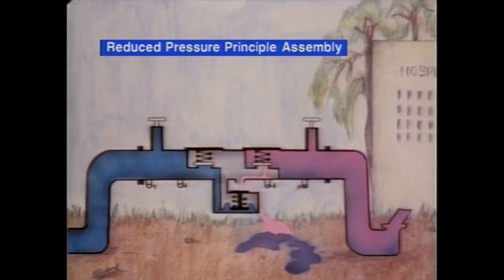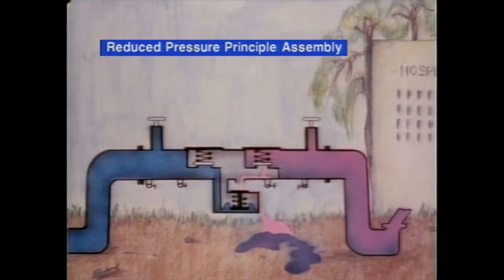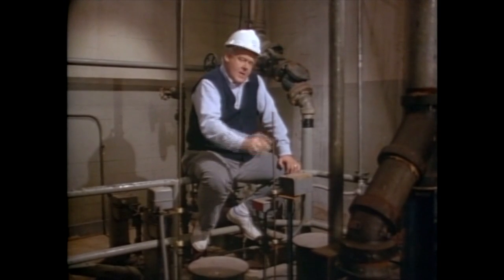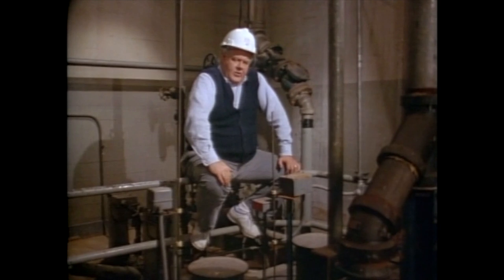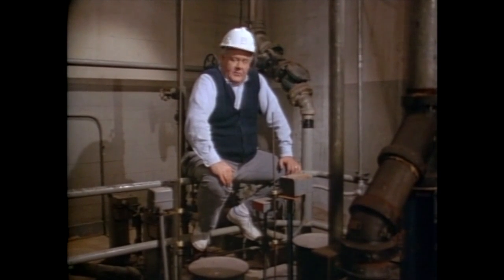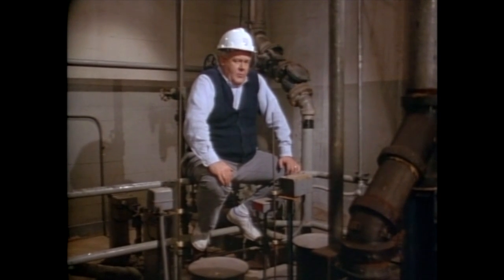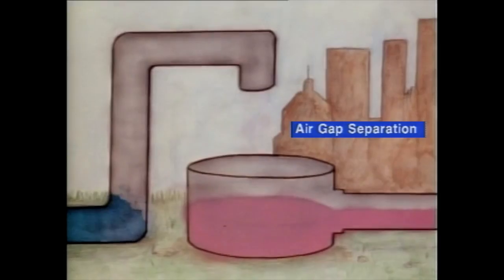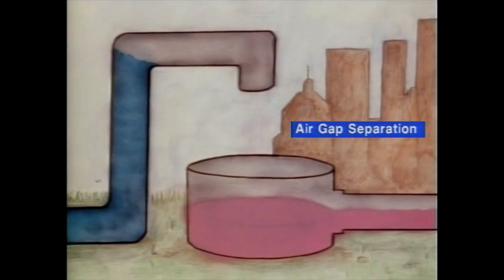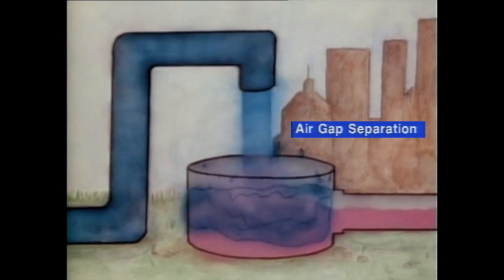However, any mechanical device is subject to failure, so an extra measure of protection is necessary in certain applications. Any time we're dealing with sewage, there may be highly toxic chemicals or lethal viruses present. In this situation, the only acceptable backflow prevention is a complete break or an air gap. Water flows through the air into a reservoir, ensuring the hazardous material never reaches the clean water supply.